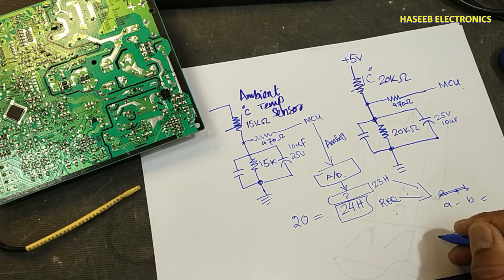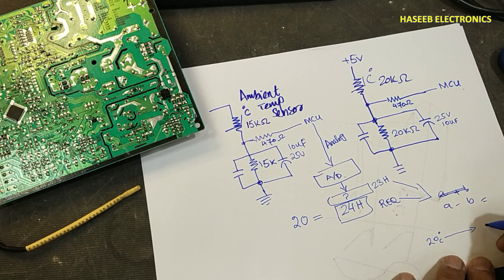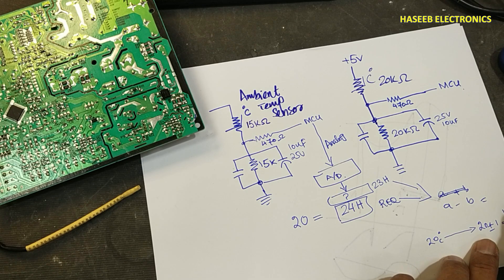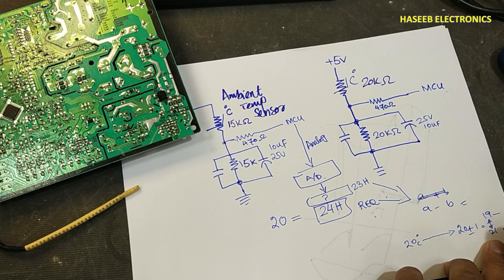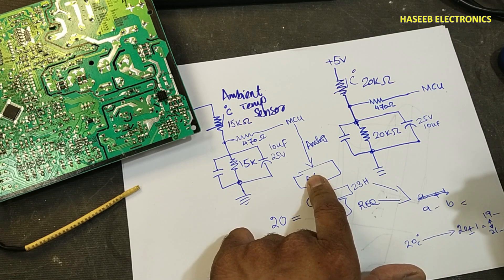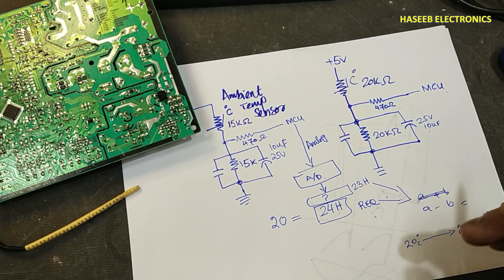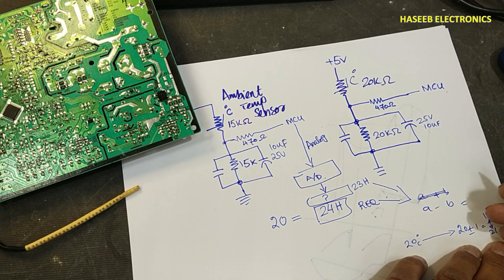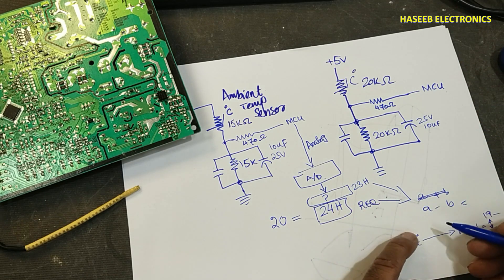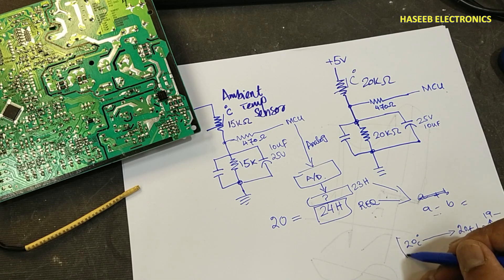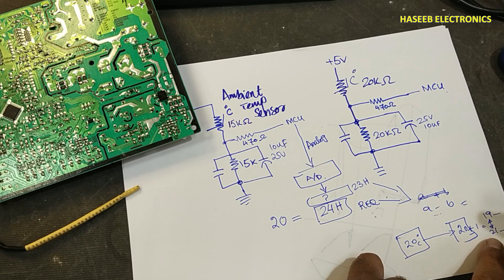The microcontroller has a defined window — for example, 20°C ±1°C (19 to 21°C). If the present temperature value is outside this window, it turns on the compressor, which starts cooling. As cooling progresses, the sensor voltage changes and the microcontroller monitors it continuously. When the present value falls within the window (required value reached), it turns off the compressor.